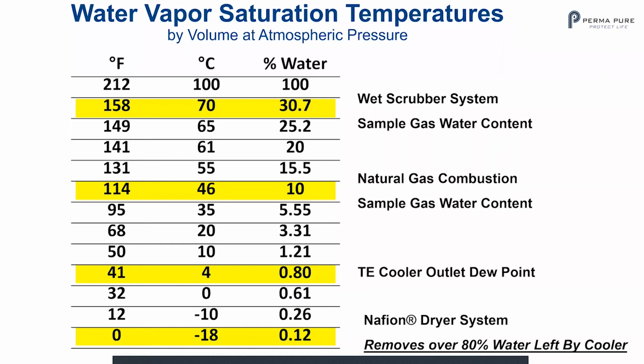These can typically overwhelm a lot of cooler-based systems, but our Nafion gas sample systems can handle 30% water without much trouble. The next level down to talk about is the water vapor present in a natural gas combustion stack. You typically have a dew point of 46 degrees C or 10% water vapor. A typical thermoelectric cooler outlet dew point gets you to about 4 degrees C or 0.8% water. That's typical. And look at the bottom there. A Nafion dryer system, typically at minus 18 degrees C dew point, will get you a percent water of 0.12, removing over 80% of the water left by the cooler.